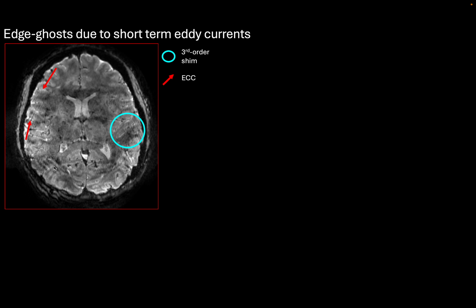And last but not least, we also have artifacts like these phase inconsistencies resulting in these weird interference patterns. And they are particularly relevant in high-resolution EPI because there we have very long echo trains, and it takes time to go back and forth and back and forth and back and forth in K-space in EPI. So any kind of phase error really accumulates along this path. So while the center of the K-space lines has a nice smooth phase evolution, so we have quote-unquote just distortions, it's much more problematic in the periphery, where we have these odd-even jumps. And they're problematic because there we have ghosting of them.